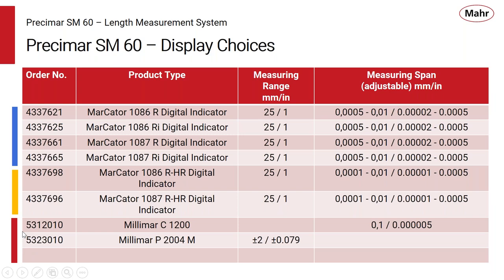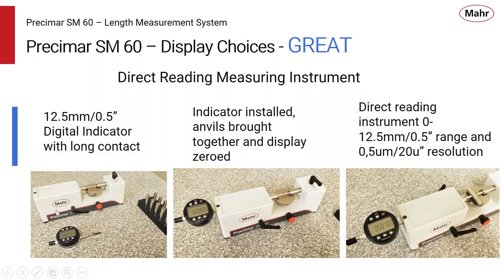And really the best performance is to use a short range, high resolution amplifier like the Mahr C1200 and its probe, and now we can get down to a 5 millionth resolution. So lots of options. I like to say the great, the better, and the best. And here's some examples of those. Here's a 12.5 millimeter indicator, half-inch range. And what we do is we put a little bit of a contact extension on this. So as we put this in, we ensure that we're within the center of the anvil's measuring setup capabilities.